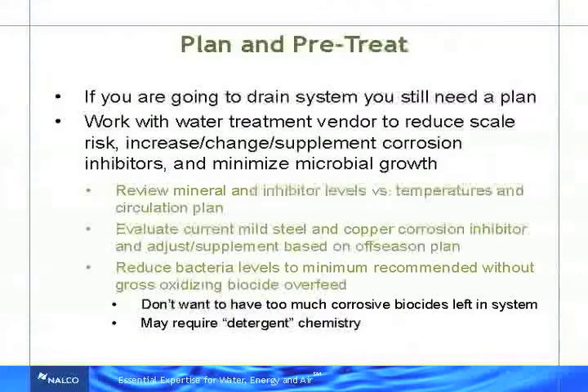So what that entails is, first, review your mineral concentrations. What happens is, and Mike kind of touched on it, we're running higher and higher cycles, 10 to 15 cycles. You've got a lot of minerals in there, and a lot of chemistry keeping them in solution. When you take that system down and you don't get a lot of flow, those minerals float around, they sit stagnant. The chemistry can kind of wear off almost, and you'll get deposition. So you'll actually get some coatings forming if you don't do something ahead of time. So you might want to drop your cycles right before you take the tower down, or bump up your scale inhibitors before you take the tower down, just to give you a little more protection.